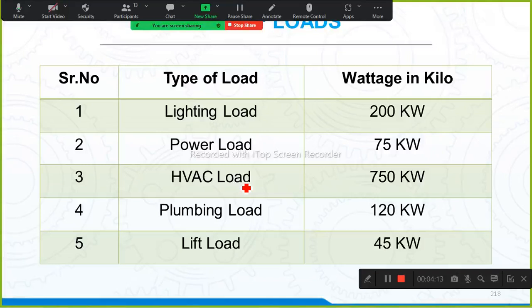Assuming these are my loads: lighting load is 200, power load is 75, HVAC load is 750, plumbing load is 120 kilowatt, and lift load is 45 kilowatt. Just assume that these are my loads for the building. Okay, these are the total loads for the building. Now we need to calculate the transformer size for this total building.